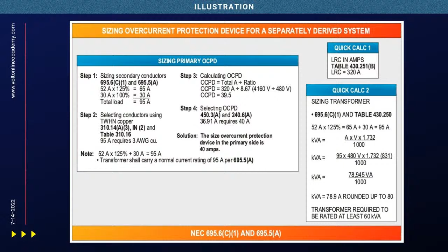I'm going to take this portion that I'm showing right here in this calculation, and I'm going to add a length here without the transformer, and do a voltage drop on this based on that running and starting current for 5 and 15%, and show the conductor size based on that. That would be sweet if you could actually get like a point at the motor doesn't start. That would be pretty sweet. Well, I want to do that because we didn't even have that calculation, and I thought we had every one of them. So I'm going to do one and put that together, and I'm actually going to add it once I get it done to the generator transformer motor compressor book, and I'll add it at the end of chapter 20 after we show that calculation. So I'm going to put that in for the 2023 cycle.